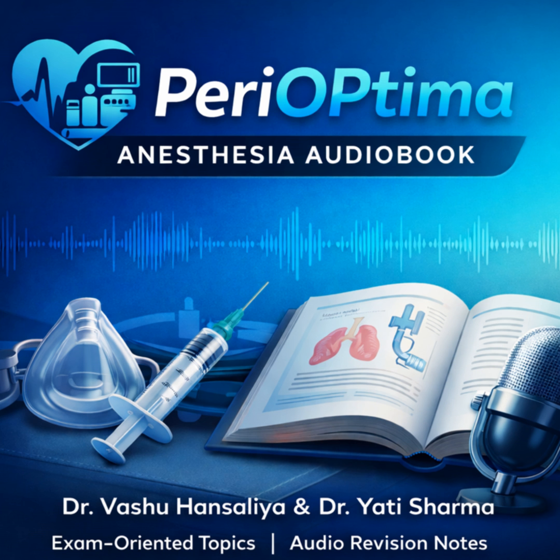Step 5. The breathing circuit itself. You perform a 2-bag test. You have 1 bag on the patient end of the circuit acting as a test lung and the reservoir bag on the machine. You pressurize the whole system to about 30 centimeters of water pressure. You check for leaks, and you ensure the APL valve releases pressure correctly when it should.